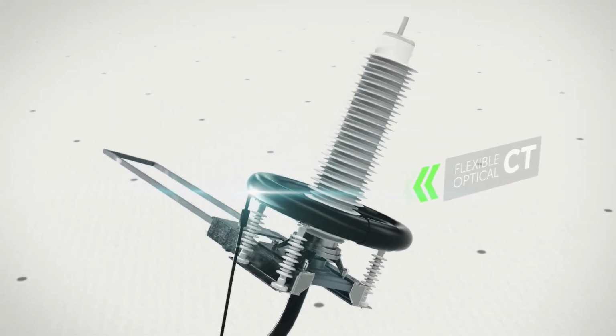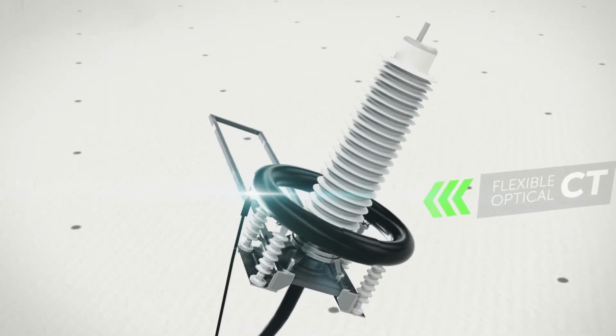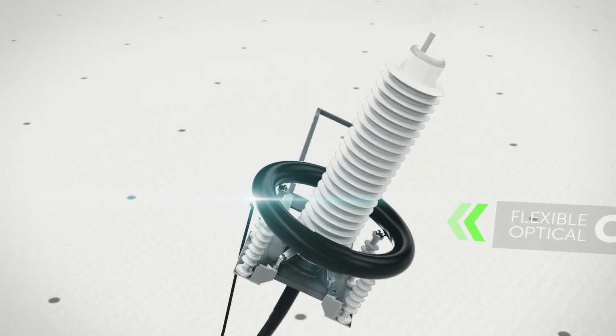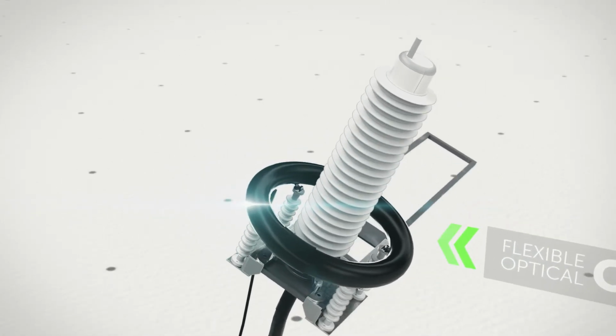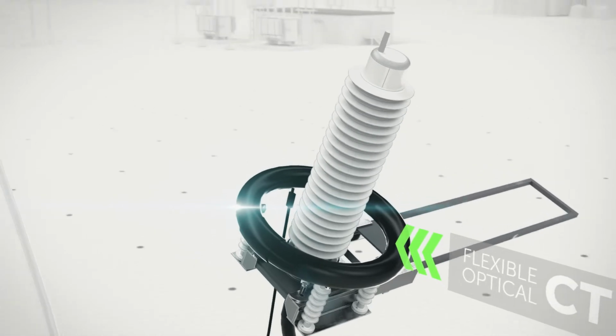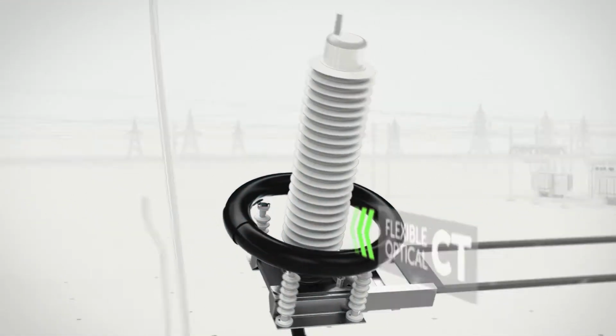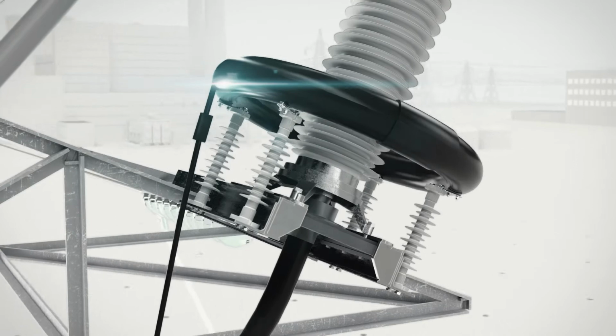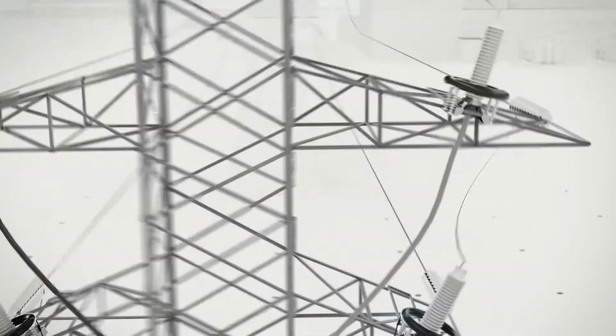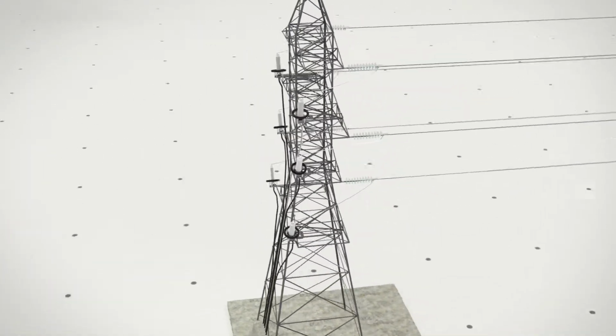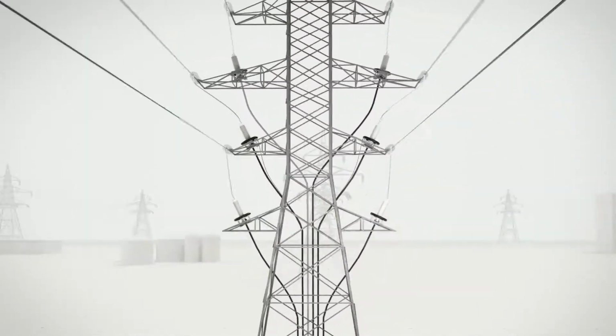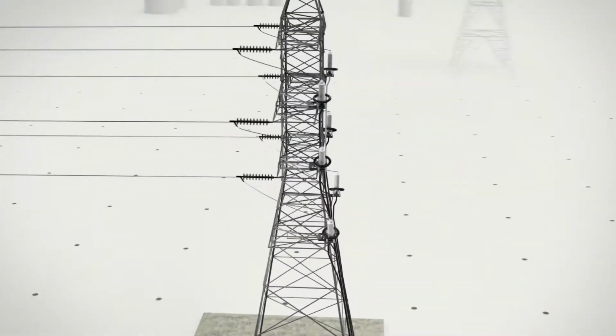Flexible optical CTs can be installed even in extremely cramped conditions, without the need for expensive construction works. The open configuration of the flexible loop renders the lengthy process of disassembling current conductors unnecessary. The optical transformer is wrapped and mounted around the cable joint, creating a point of measurement right at the junction between the aerial and the cable lines.